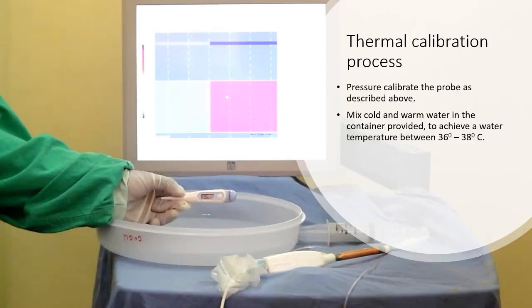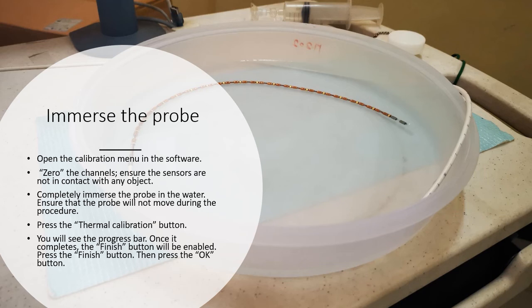To perform a thermal calibration, first pressure calibrate the probe as described above. Then mix cold and warm water in the container provided to achieve a water temperature between 36 and 38 degrees Celsius. Then open the calibration menu in the software. Zero the channels, ensuring that none of the sensors are in contact with an object. Completely immerse the probe in water.